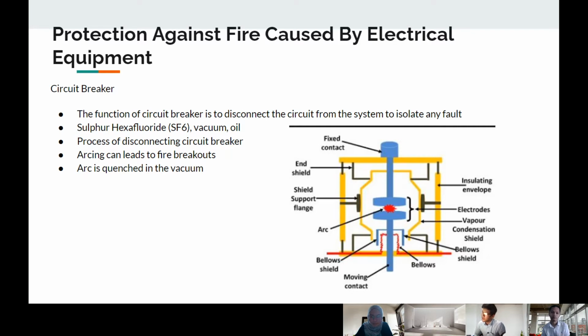In a vacuum circuit breaker, there are a fixed and a moving contact, which are housed permanently inside a steel vacuum ceramic bottle. Whenever the contacts are separated, the arc is immediately quenched since the contacts are in the vacuum ceramic bottle. One of the properties required before ignition or combustion takes place is air, which contains oxygen. Without the presence of oxygen in the vacuum ceramic bottle, there will be no process of ignition or combustion at the contact. Therefore, when no arc exists, the chance of fire breakouts happening is very minimal. Next slide.